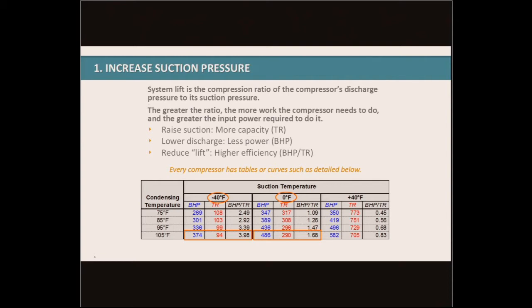Compressors are going to be the largest energy-consuming piece of equipment in a refrigeration system. Talking specifically about increasing our suction pressure — when we do that, we increase the capacity of the compressor. By increasing the capacity of the compressor, we're making it more efficient. It's able to do more tons of refrigeration for less brake horsepower. If we lower the discharge pressure, we're using strictly less brake horsepower.